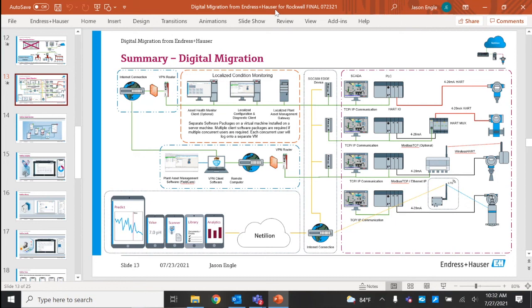That's exactly correct. So that's just something added to the PLC system? It would be added into the cabinet, and as you can see on the slide, the edge device can be added into all the different setups, from 4 to 20 HART all the way down to Ethernet IP. So you're adding an edge device into the cabinet, allowing one-way communication to send the data to the cloud, which also accomplishes the security requirement. You're not sending signals into the DCS that would disrupt anything, but it provides the data, allowing it to go out and be easily configured into an app of some sort to provide additional value.